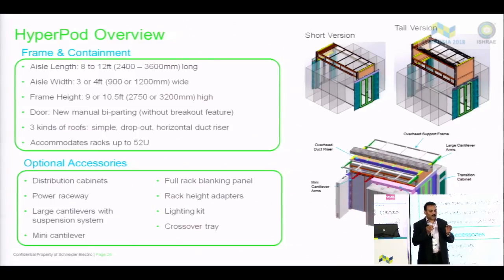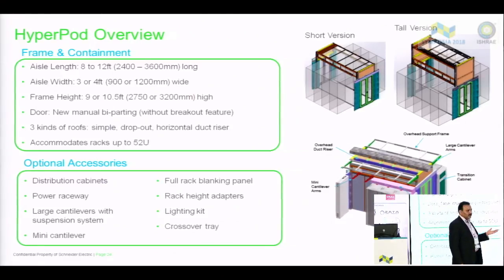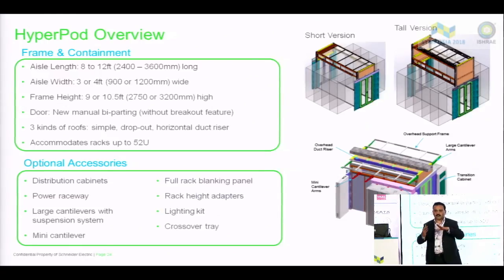So we have seen practically that when you take measurements on paper and design things, and when you actually deliver it, there are a few mm of gap. Now these gaps can be easily adjusted in a hyperpod. You don't need to redesign things at all. It doesn't matter that your original design was for 42U and you have gone for 52U. If it is part of your plan, it's possible to even accommodate a higher or lower IT cabinet.